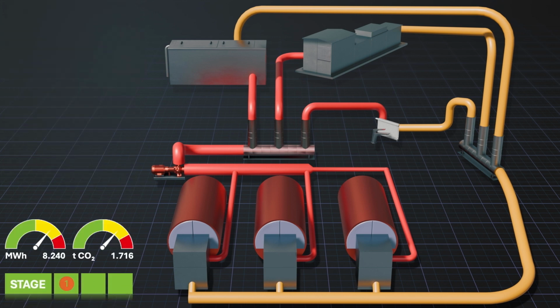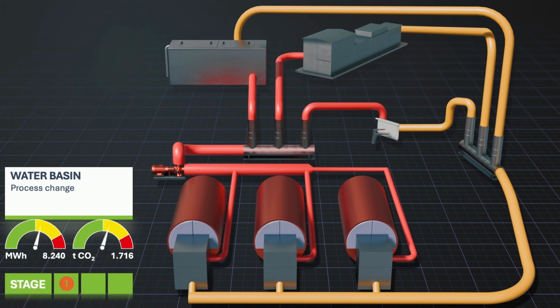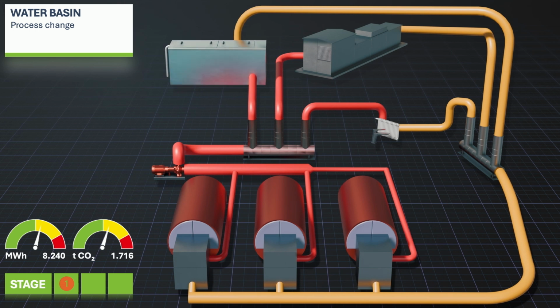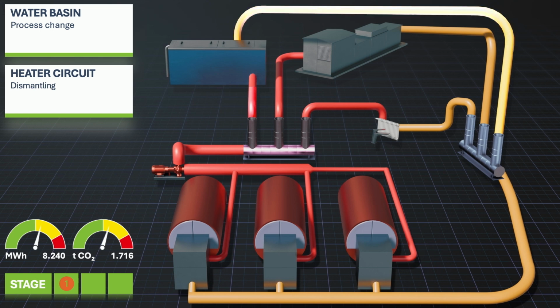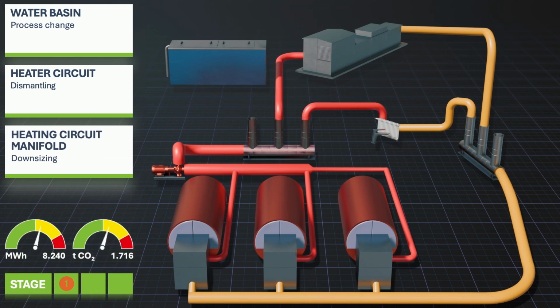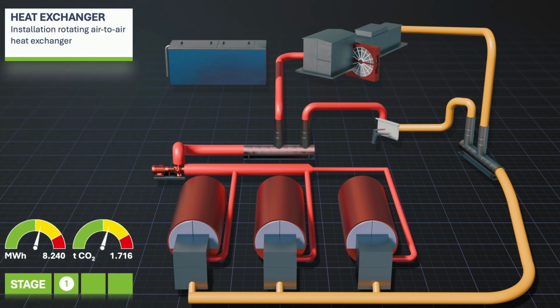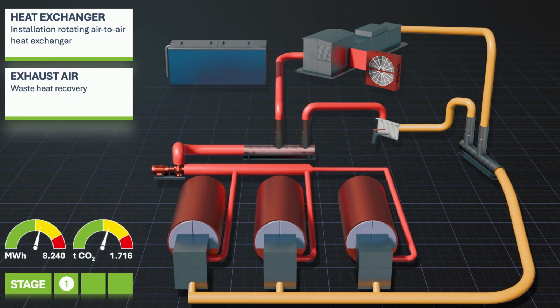These 3 measures, optimized process, heat exchanger, lowered temperature, can be implemented in a first construction phase. This means that the heating circuit to the water basin of the paint shop can be dismantled and the entire heating circuit manifold can be reduced in size. By using heat transfer in the form of a heat wheel in the ventilation system, the heat requirement for heating the hall can be significantly reduced.